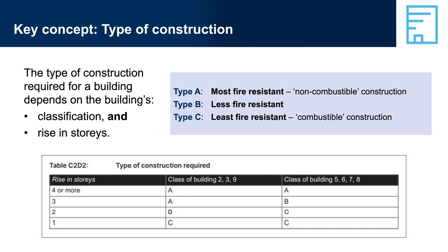Special rules include C2-D4 for two-storey Class 2, 3 or 9C buildings; C2-D6 for Class 4 parts of buildings; and C2-D7 for some buildings that can have more than one type of construction. The requirements in Table C2-D2 are DTS provisions and a designer-builder always has the option of developing a performance solution to meet the performance requirements.